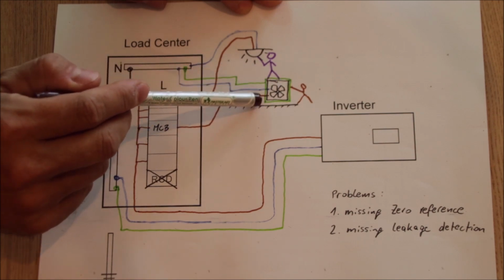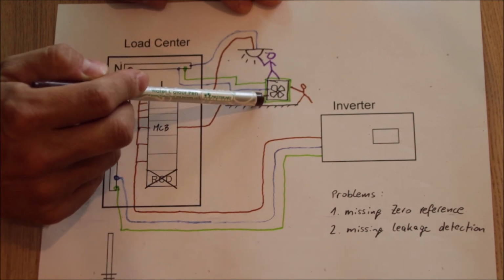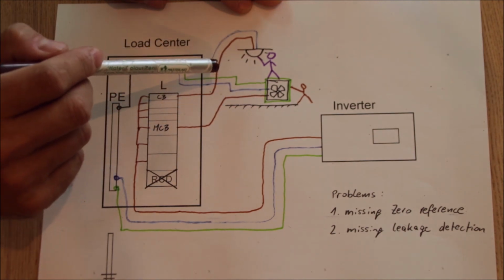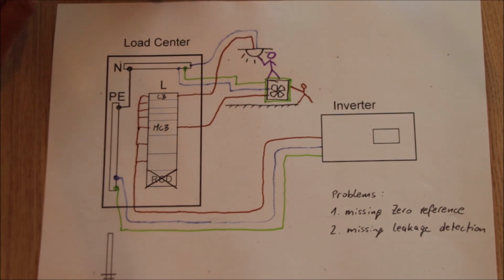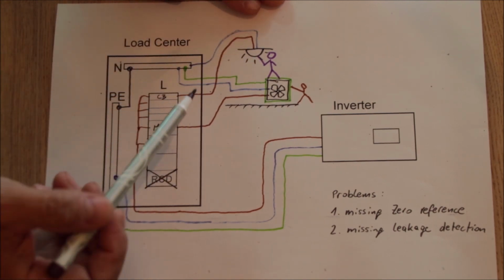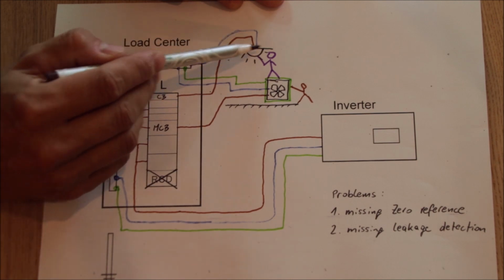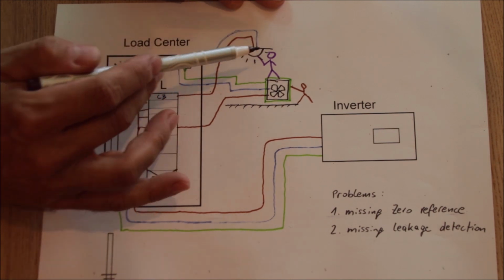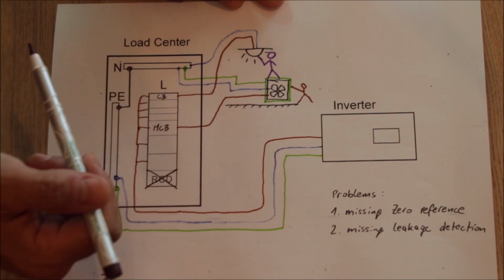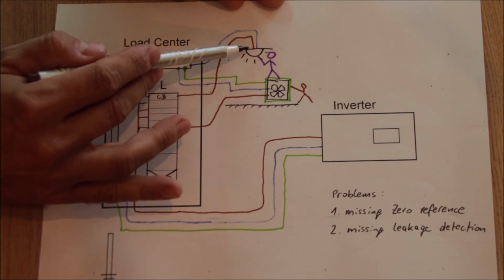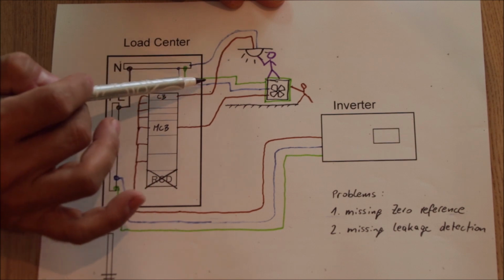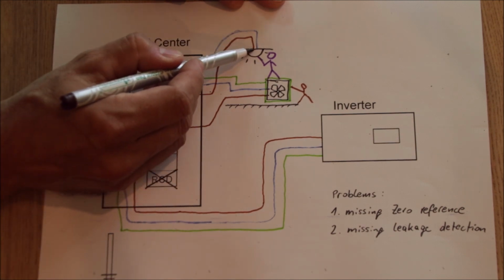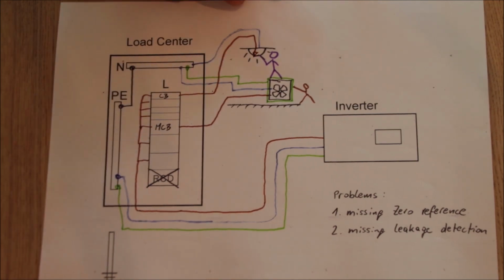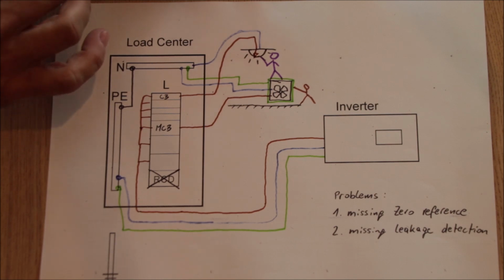The second issue is that because we have exposed now one of the active wires, we only need one extra fault, which is kind of including a L, and then something really terrible can happen. So in this case, that is what I have drawn up here. Let's say we have another circuit right next to our air conditioning compressor. We have installed a light fixture. The light fixture shall have a metallic casing here, and because, you know, electricians have been lazy, same here in Thailand, they never put a earth wire to a light. So we only have neutral, we only have L, and now let's say we have a fault here, L touching the metal a fixture of the light.